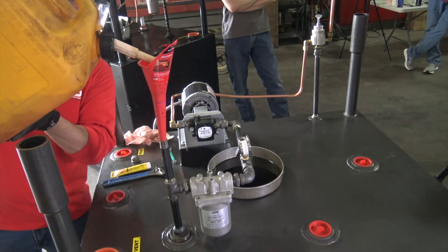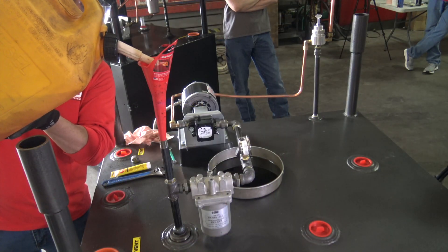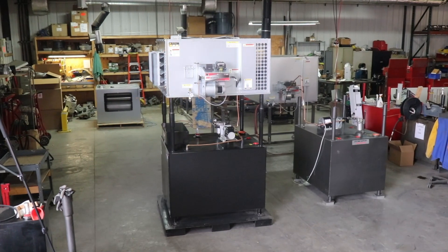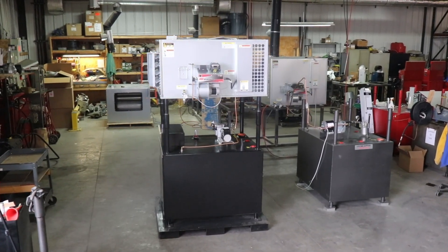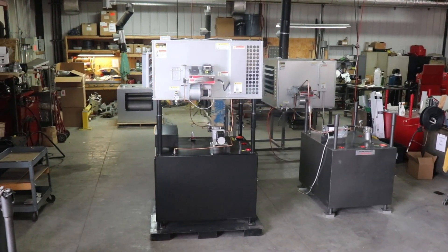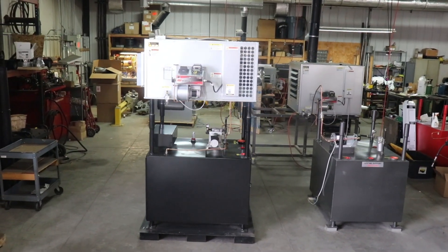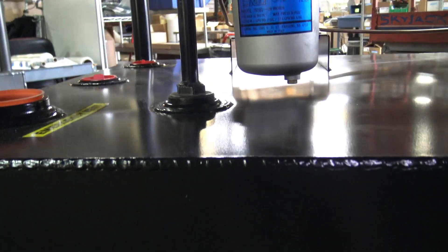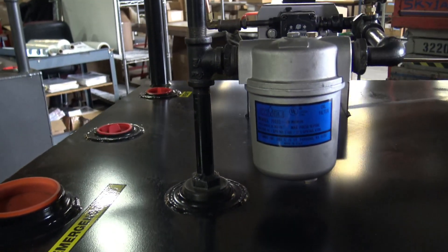Most firing issues stem from fuel quality rather than the function of the unit. Always be sure to collect and store your fuel according to the guidelines provided in the product instruction manual. Avoid the collection of water, antifreeze, gasoline, debris, and other contaminants and unapproved fuels, and be sure to service your collection tank annually to remove any of these that may have been collected accidentally.